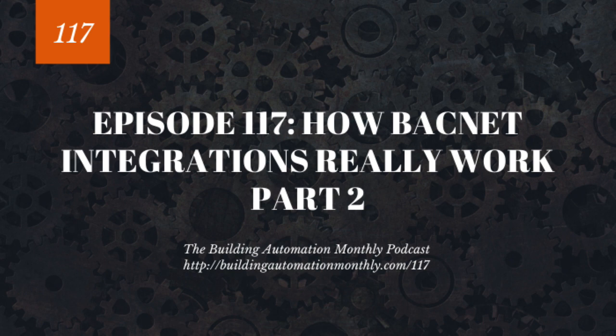Also, another one I've seen happen is end of lines. If you have a trunk that's working just fine, and then you replace the controller and all of a sudden at that controller you can't see anything else down the line, usually that means someone accidentally crossed the polarity of the wires, meaning they put the positive on the negative and the negative on the positive, or they turned on the end of line by accident.